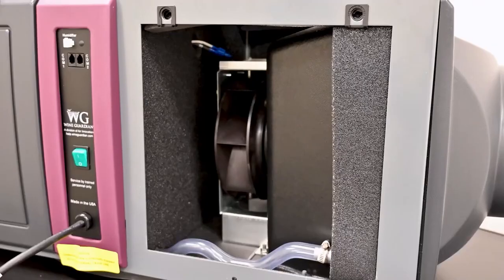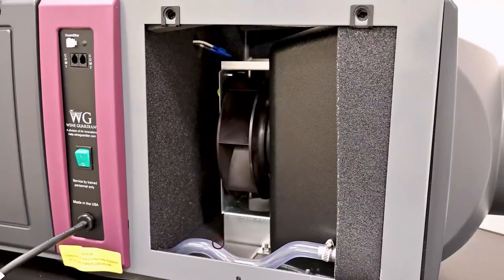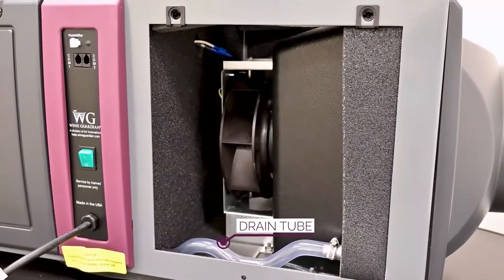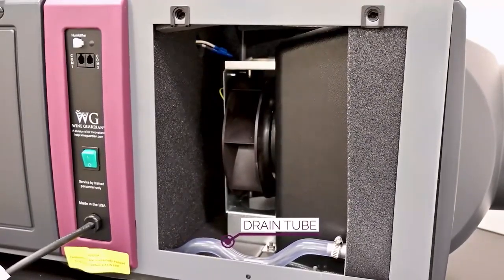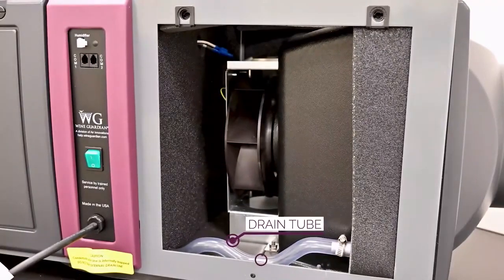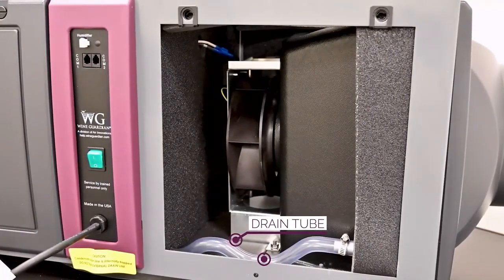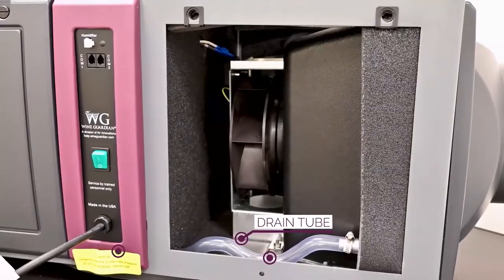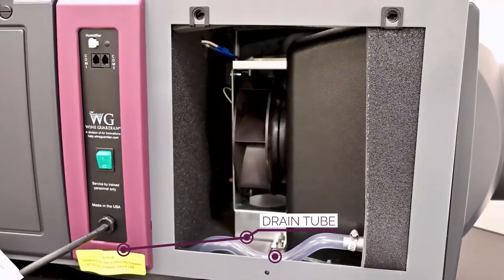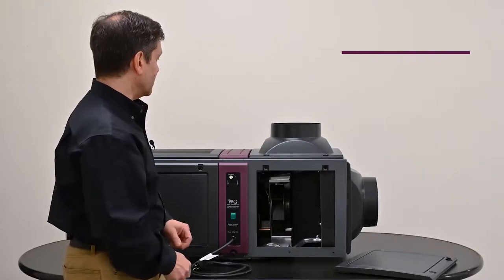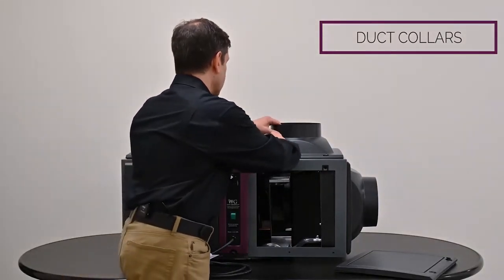Okay. You'll also notice that we have a drain tube here, which is part of the design. You also note that that drain tube has a trap internal to it. That drain connects to the bottom side of the unit. So let's look at the duct collars here. I'm going to remove this duct collar.